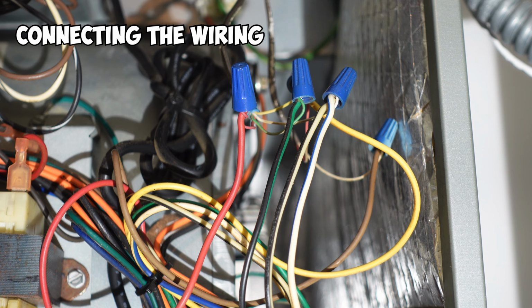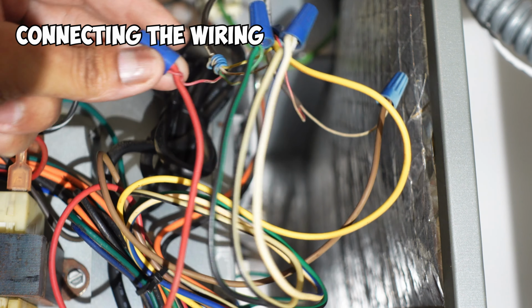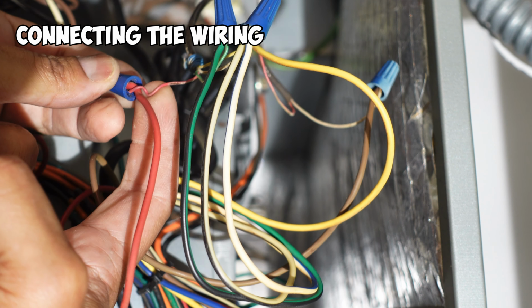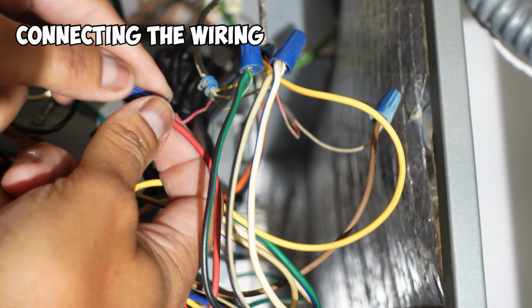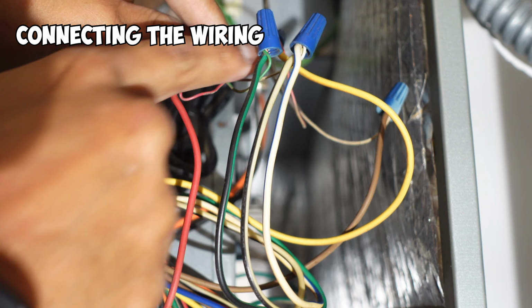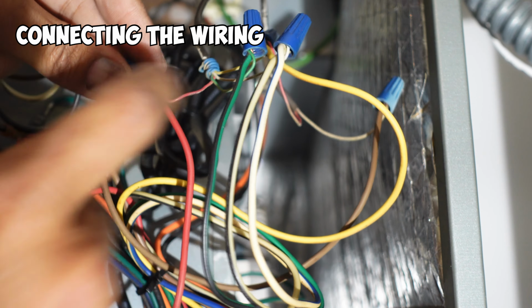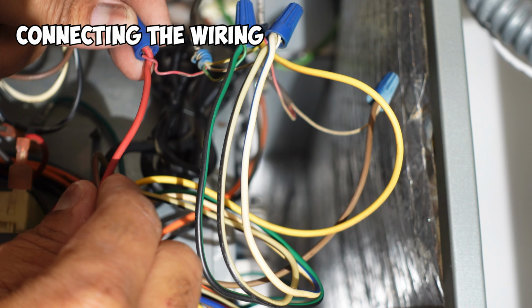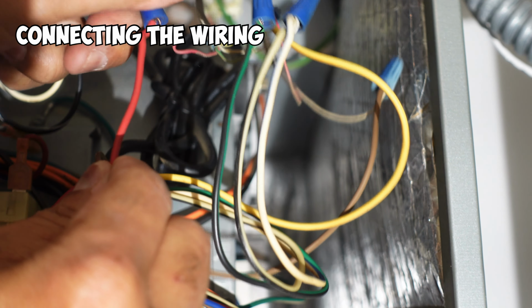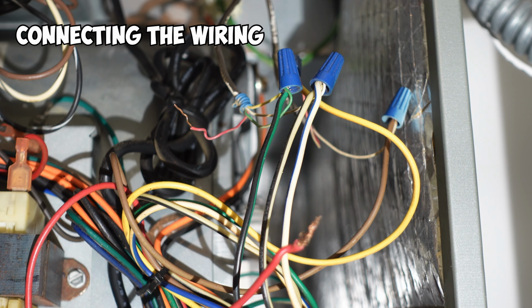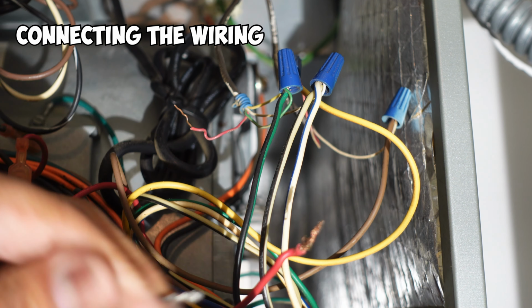Now let's get to the fun part. You want to locate the red wire coming from your thermostat. Usually this is connected to another red wire coming from your motor. Once you've located these wires, you're going to separate them. Usually if they're held in place by a wire nut, you just loosen the wire nut and separate the two wires. Now, coming from your float switch, you're going to have two wires as well.